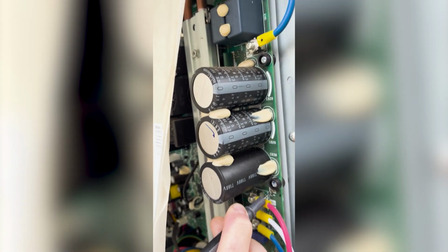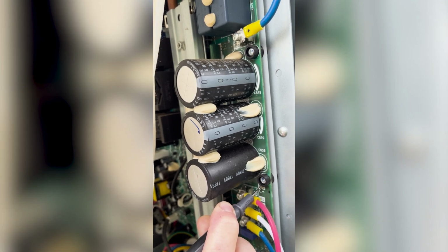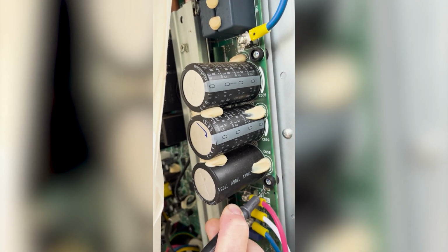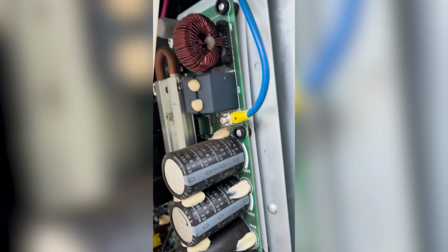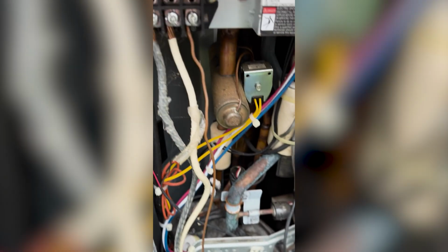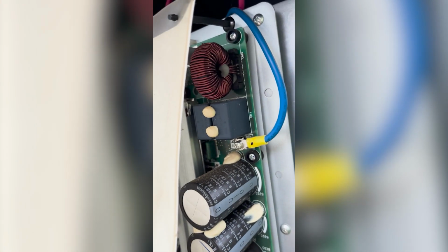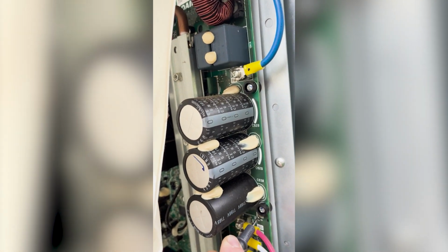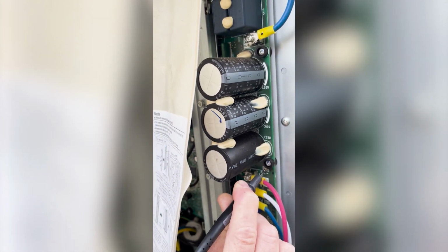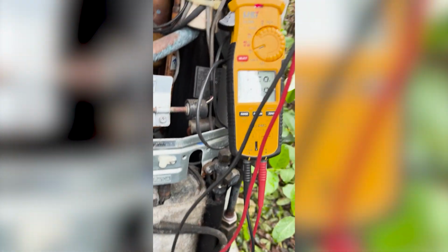This matters because you have to remember that these giant banks right here, these capacitors on the side, they store voltage, right? For an inverter system to operate, we're not only just taking the AC voltage 240, 208 that we get here at the terminal, we're also converting it to DC voltage, charging these capacitors, and then allowing the board to use its IGBTs to simulate voltage, right? Simulate that AC voltage to run the compressor.